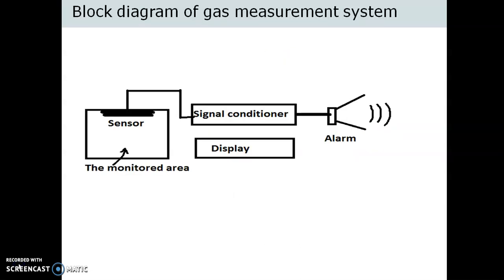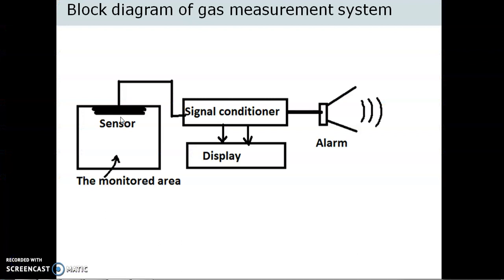Now, let us understand the block diagram of gas measurement system. A suitable semiconductor gas sensor is placed at the top ceiling of the area to be monitored. The output of the gas sensor is applied to a signal conditioner that consists of Wheatstone bridge circuit, power supply, and amplifier. The signal conditioner output is then given to an alarm or display. As soon as the presence of the particular gas goes above the predefined value, the resistance of the gas sensor decreases significantly and the alarm is turned on.